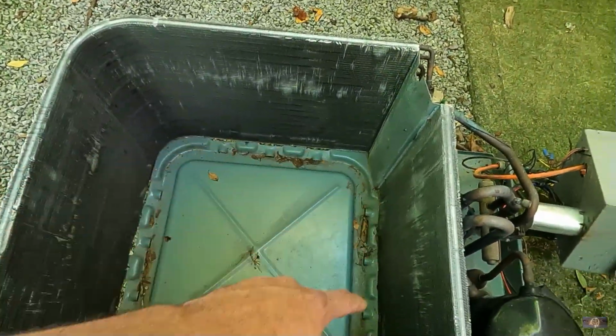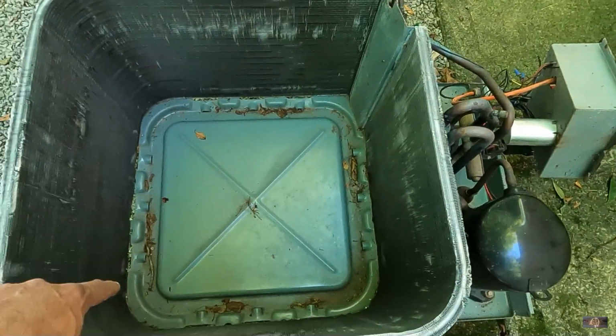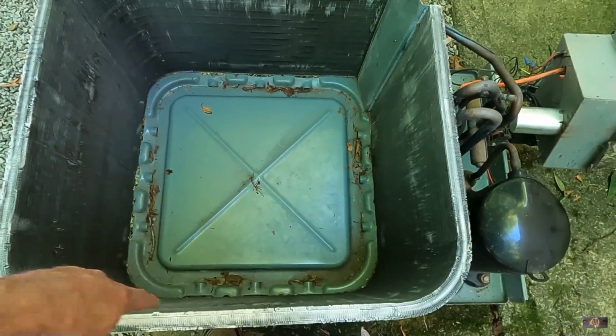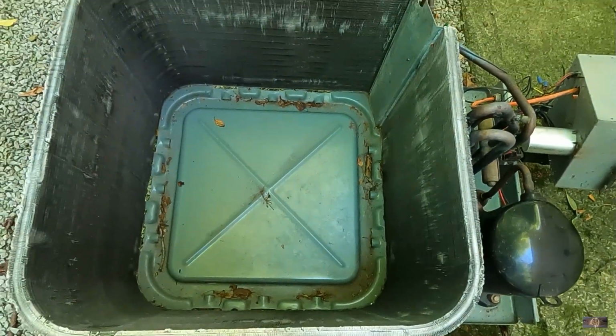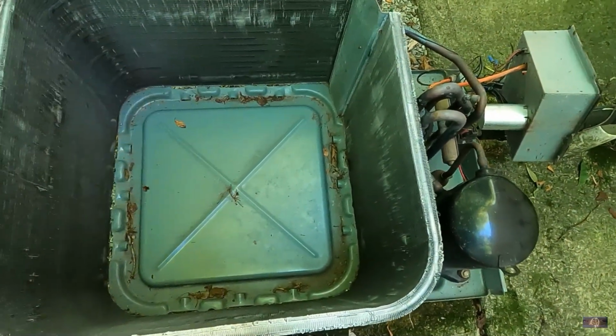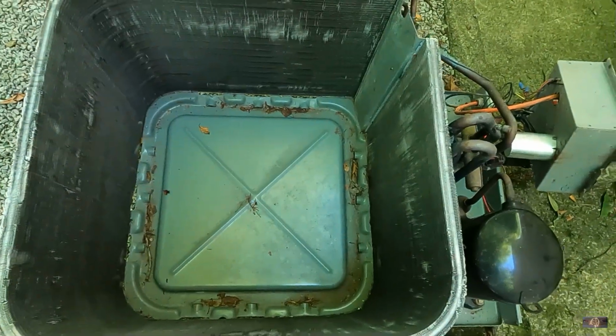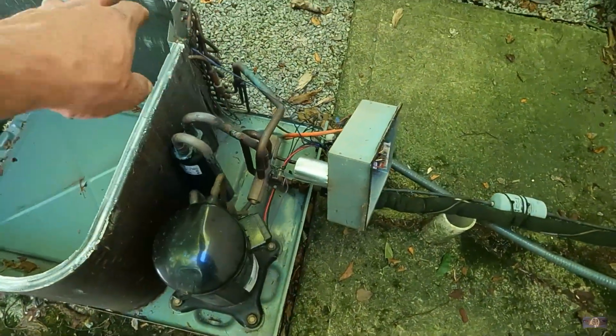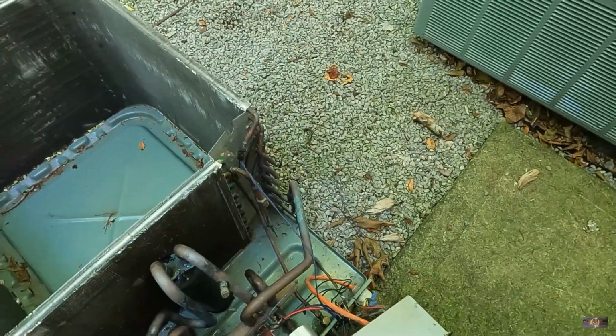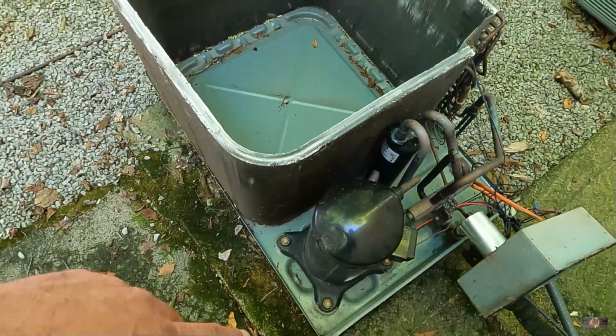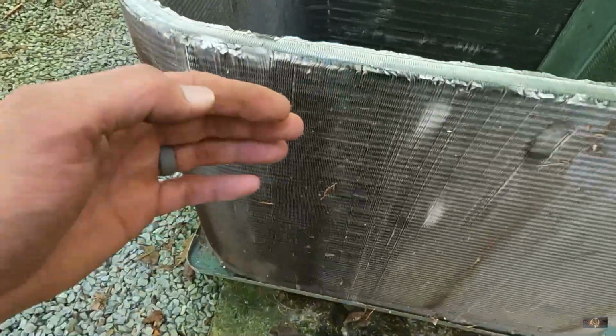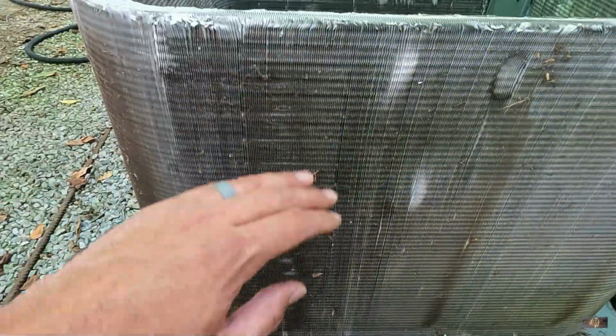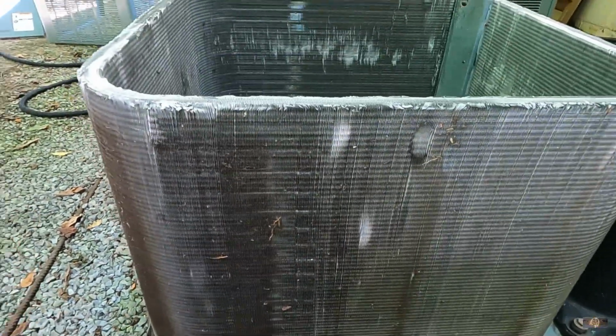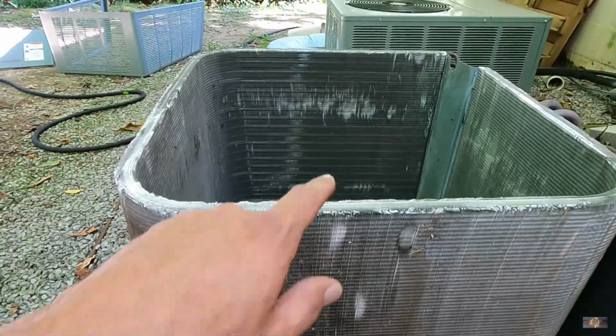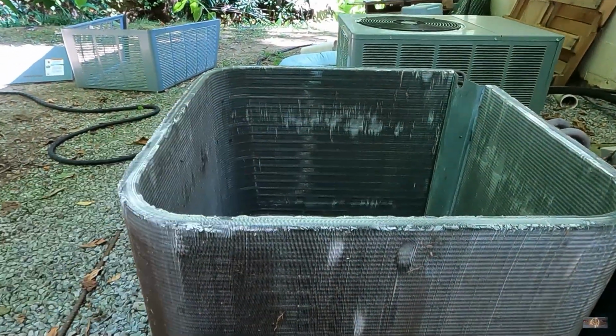But you can see here we got a little debris in it. I always like to get the big debris out first. I put some gloves on, take the debris out before I spray it with water. That way it's easier for me to just get it out, or I can use a shop vac or something like that. I'll go ahead and dry clean all the cobwebs out of this thing with my condenser whisk and get that thing cleaned out. All this debris on the coil here, I'll hit that with my dry brush, wipe down on that, get that all off of there, and then I'm going to spray it with water only, no cleaner, and I'm going to go from the inside out all the way around.